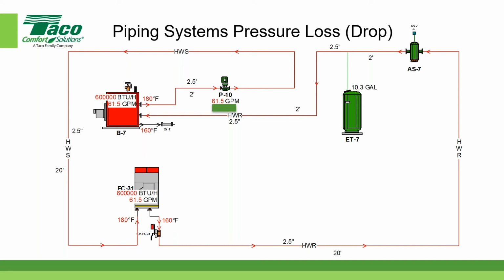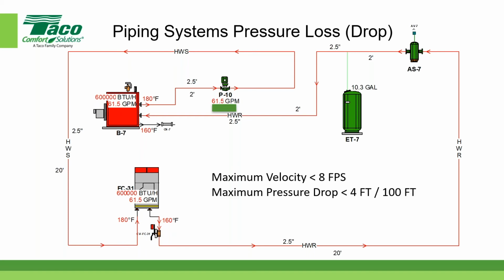But the very first thing I want to do is number my piping system from point to point. My very first point, and this is a bit arbitrary, I'm going to pick at the discharge side of the boiler and call that point 1. So I'm going to fill in all of the points by numbering them. Oh, that's the other thing I want to say. In terms of sizing this pipe at 2.5 inches, I wanted a maximum velocity of 8 feet per second, in other words a velocity less than 8 feet per second. And I also wanted to meet the criteria of a maximum pressure drop of 4 feet per 100 feet.